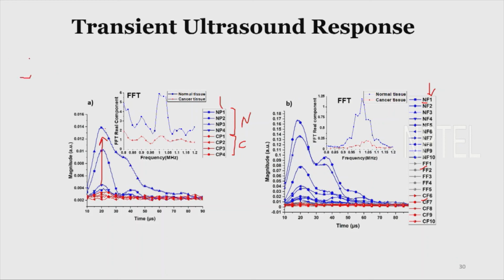Please note that the input that goes into the system is a pulse of 500 nanoseconds. So the system sends this pulse of ultrasound through the tissue, and what we detect is the result that you see here.